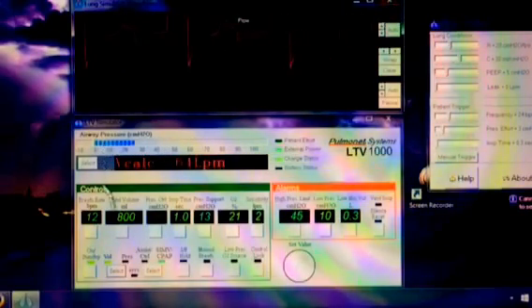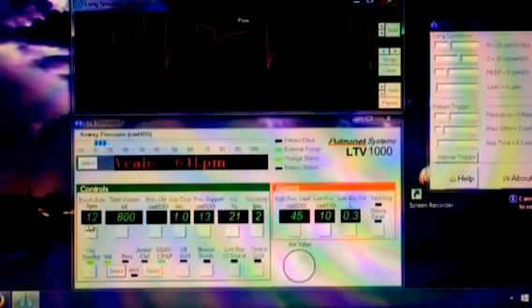If it goes above 45, it will alarm with high pressure. It'll stop that breath immediately and let the patient breathe out, and then it'll try again with the very next breath. That high pressure limit is usually indicative of congestion, phlegm building up, bronchospasm, or inflammation of the airways.